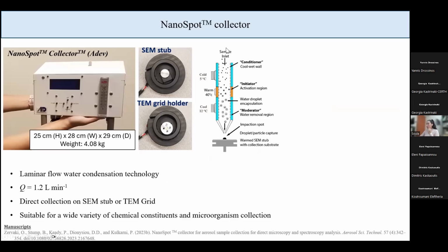First, we have the aerosol flowing through 3 different stages. First, it flows through a cold stage, the conditioner, which cools the aerosol flow and humidifies it. Then it flows through the initiator stage, where the wick that surrounds the aerosol is heated to high temperatures, releasing vapor across the radial axis of the aerosol stream. And then because the vapor diffuses faster across the radial axis than heat does, we have generation of supersaturation, and then vapor activation on the surface of the particulates and subsequent droplet growth.